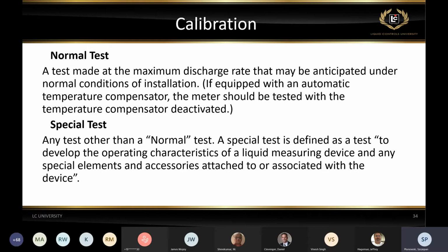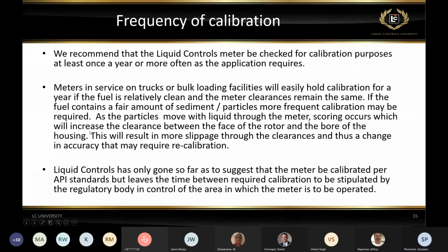The special tests are any other test performed on the metering system. There could be a number of them, from low flow testing, when you're checking the linearity of the meter, to a split compartment test, also called a depletion test, or any other test related to that metering system. So: a normal test and a special test.